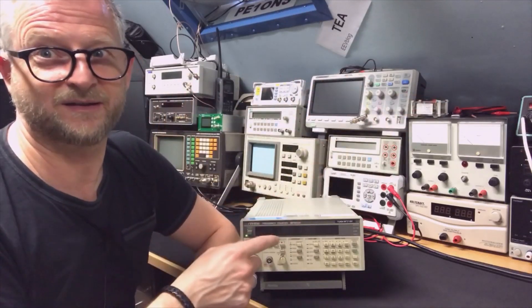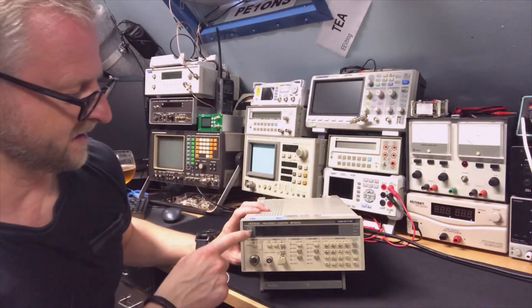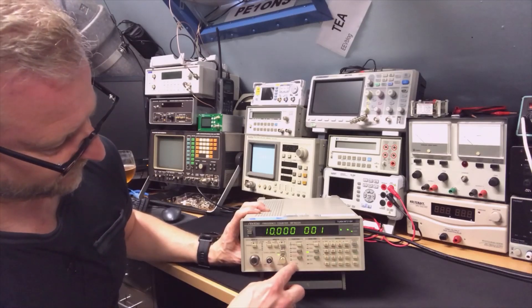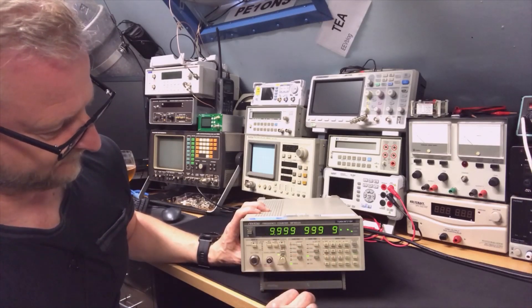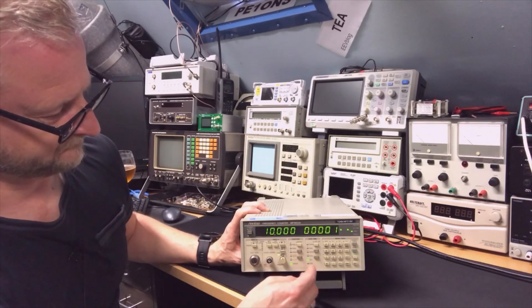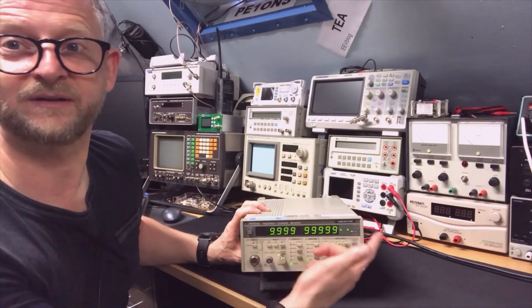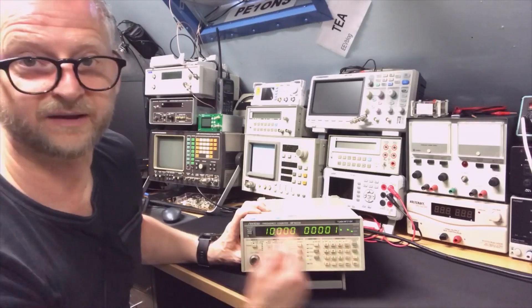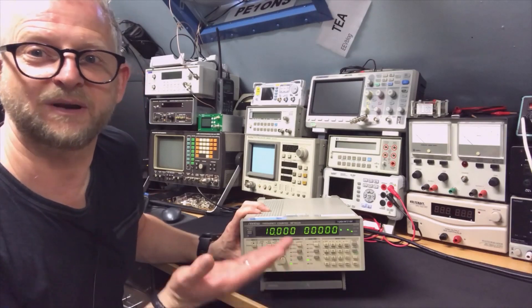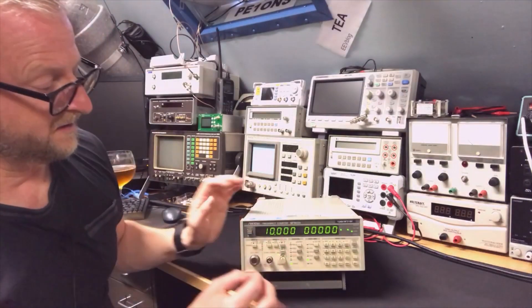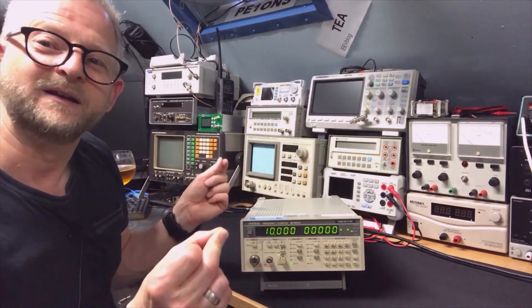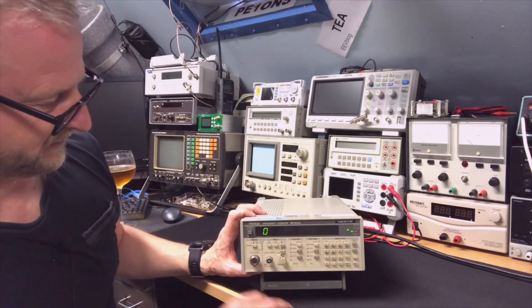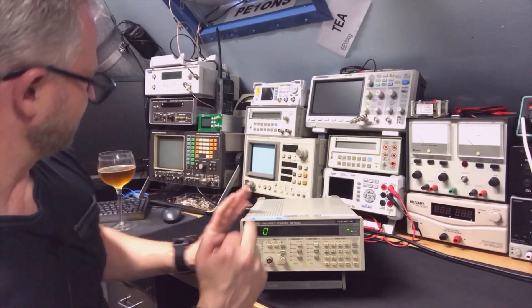The standby is really low, and if we switch it on it seems to go to some internal test. It's nice - you can cycle through. It says 10 because it's referenced to itself, so of course it will be 10. You will have some variations because the oscillator is still heating up, so it's not stabilized yet. Even testing with itself during the count period it is already changing, so you will see the frequency change.